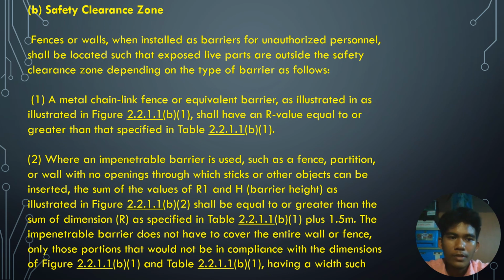Safety clearance zone. Fences or walls, when installed as barrier for unauthorized personnel, shall be located such that exposed live parts are outside the safety clearance zone, depending on the type of barrier as follows: a metal chain link fence or equivalent barrier, as illustrated in Figure 2.2.1, shall have an R value equal to or greater than the specified in Table 2.2.1, where an impenetrable barrier is used, such as fence, partition, or wall with no openings through which sticks or other objects can be inserted.